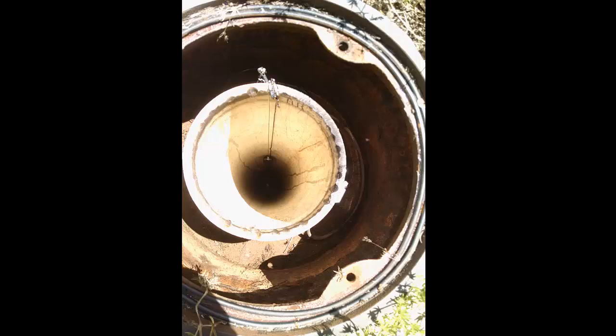When you deploy a water level logger underwater, it's important to have it deep enough so that if you're doing, for instance, slug testing, as you drop that slug into the well and remove it, it doesn't bump into or interfere with that deployed water level logger. But you also don't want it so deep that you begin to damage the sensor itself. Since our sensors are rated to 13 feet, your target should probably be around 7 feet beneath the static water level. So if you're using a slug that's, say, 5 feet long, and you drop it into the well, you have, say, 2 feet of space between the logger itself and the bottom of the slug, but the logger won't be so deep that you begin to damage the sensor.